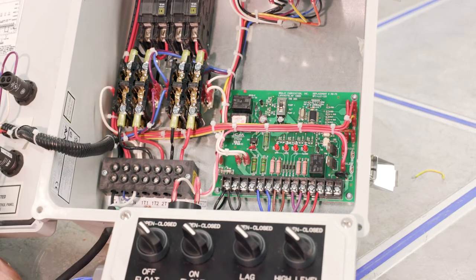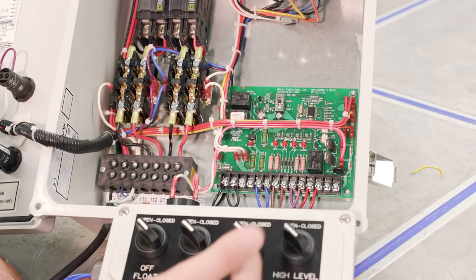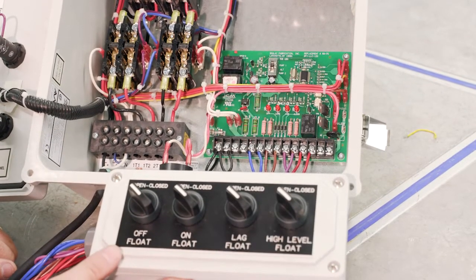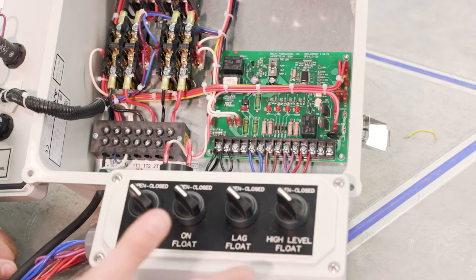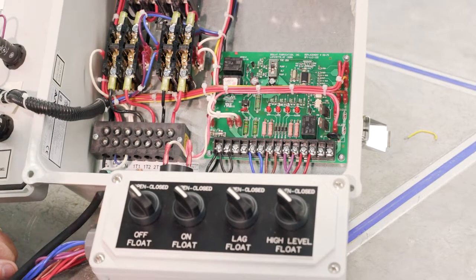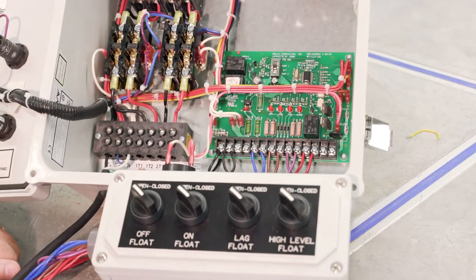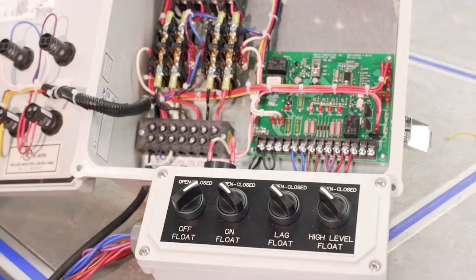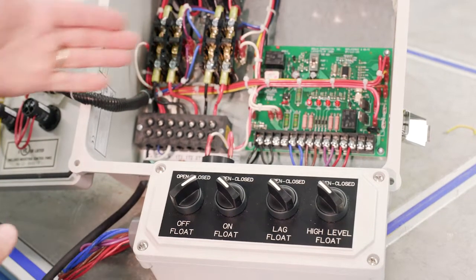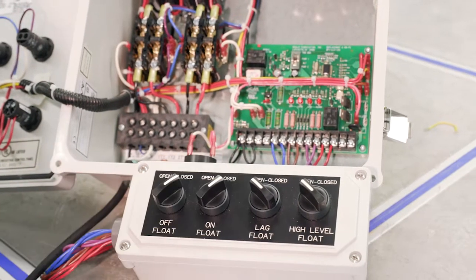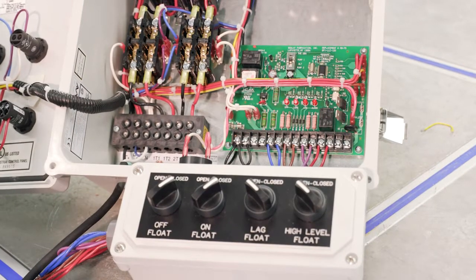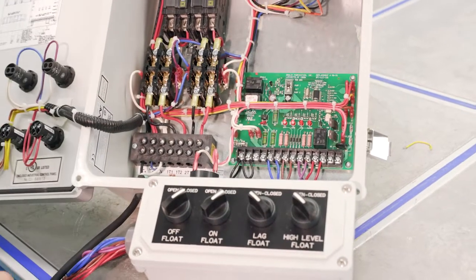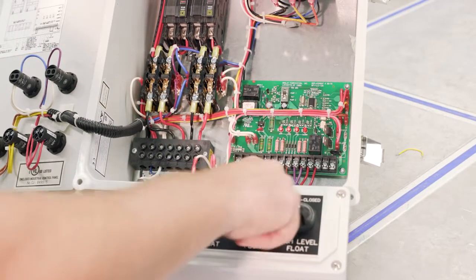One last scenario is lag pump does not keep up and it gets to the high level float. So it's going to get a little noisy, the alarm should come on, the buzzer should come on, and so let's go through that one last scenario. Off float, nothing happens other than the light. On float, it's alternating again. So pump one is on, can't keep up, gets to the lag float.